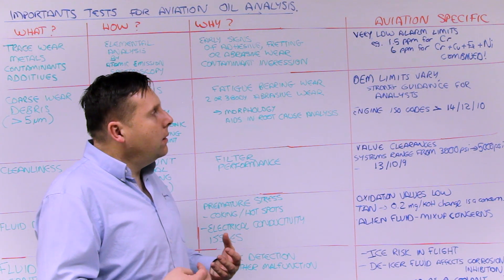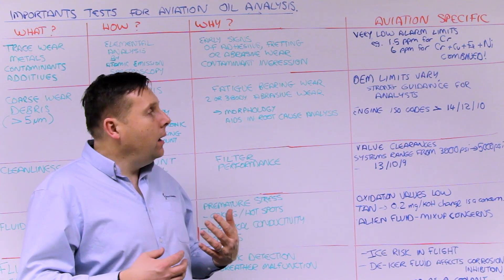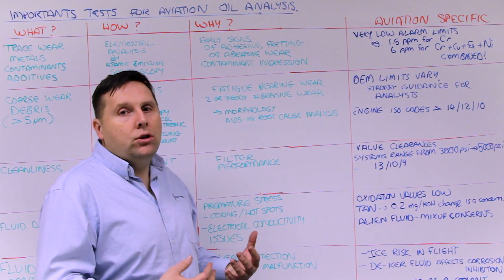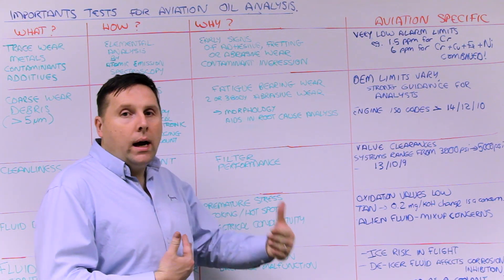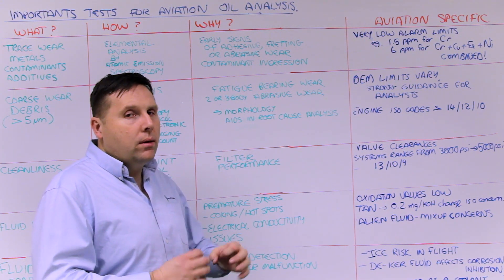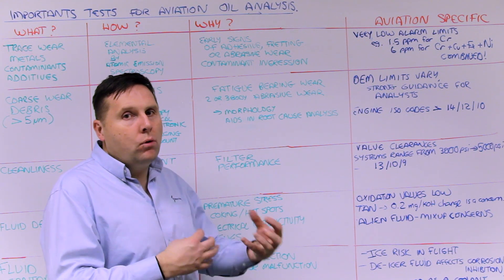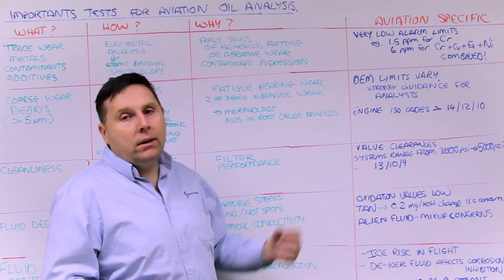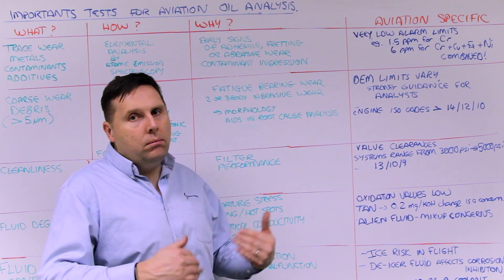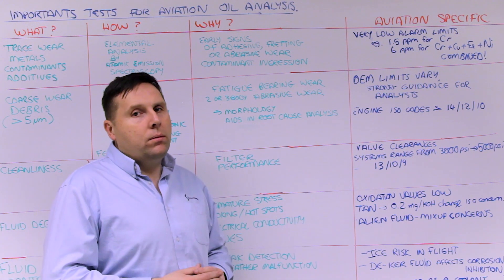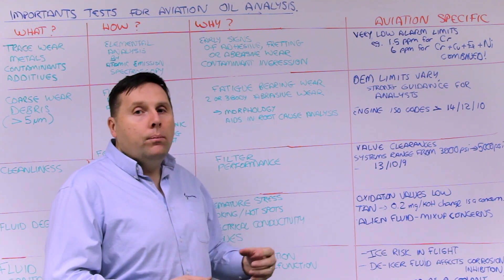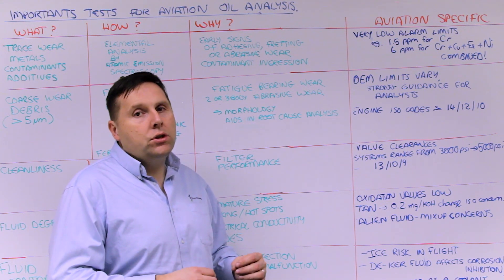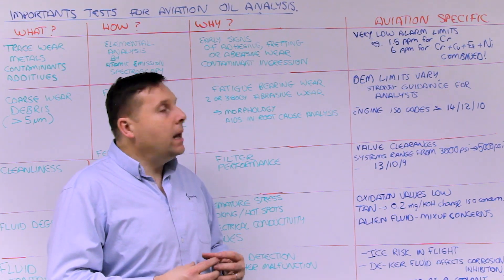Morphology is very helpful in aiding root cause analysis. What's unique to this industry is that OEMs provide very detailed information to the end user through guidance and diagnostic documents covering the size, shape, morphology, and alloy content of debris. Engine ISO cleanliness codes are generally exceptionally clean — ISO 14/12/10 and below for total particulate is not unusual — with specific focus on alarms that are ferrous or metal-based.